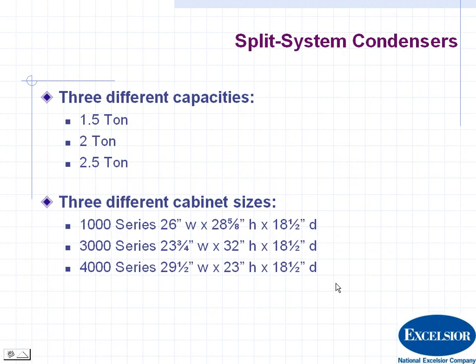Let's talk about the split systems first, and they do also have a heat pump line. So this goes for split system condensers and heat pumps. But there's 3 different capacities. There's a 1.5 ton, 2 ton, and 2.5 ton. You really don't need any more than that in multifamily if you've ever done any multifamily work, because there's not a lot of outside walls, not a lot of infiltration. So 2.5 ton is probably the largest you're going to need.